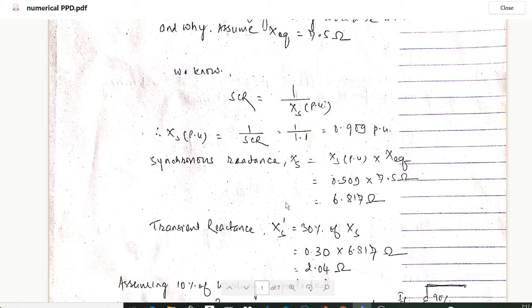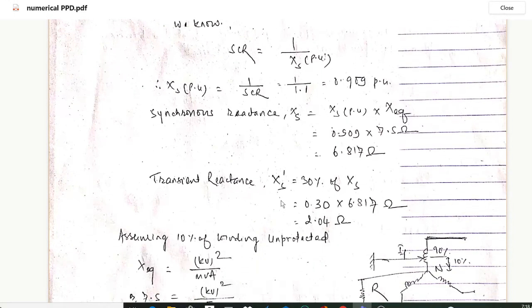Similarly, the transient reactance: in order to calculate the transient reactance we have to consider 30 percent of this synchronous reactance. So 30 percent of synchronous reactance will be 0.30 into 6.817, and on calculation we will get 2.04 ohms.